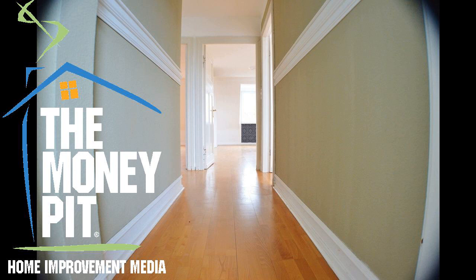So the only thing that you're using that water heater for on that side of the house is the dishwasher, and that's a 50-gallon water heater? Yes. Wow. Well, like I say, this house was actually set up to be a bed and breakfast. If the only thing that water heater is serving is the dishwasher, and there's no way to get that dishwasher fed off of the other water heater, you just need a very small water heater for that dishwasher. And I mean like a 20-gallon electric or something like that, really small, because there's really not much water that it needs to heat. And it would be foolish to have it heating 50 gallons, 40 gallons of water 24/7 when you really don't need it except to wash dishes and I presume to run the kitchen sink. So a very small electric water heater, perhaps even on a timer, so that it only kicks on maybe in the evening hours when you're using that dishwasher, would be the smart thing to do there in the least expensive way to both install the new water heater and to run the new water heater.